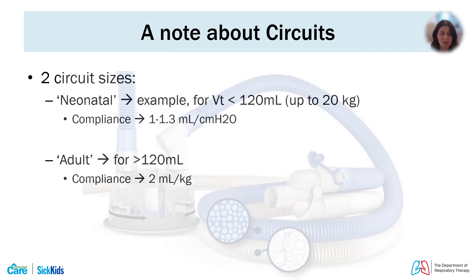On occasion we get asked what size of circuit we use in pediatrics. We follow device manufacturer recommendations for circuit sizing. Generally speaking, there is not a single pediatric-sized circuit — we use both neonatal circuits for our smaller patients and adult-sized circuits for our older patients. They do have different compliance ranges in terms of how much volume is lost to the circuit.